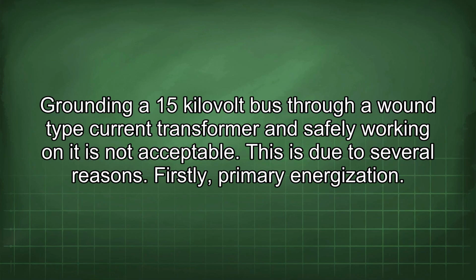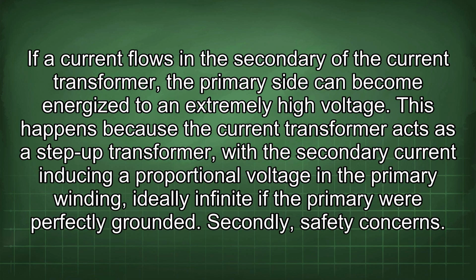Grounding a 15 kilovolt bus through a wound-type current transformer and safely working on it is not acceptable. This is due to several reasons. Firstly, primary energization. If a current flows in the secondary of the current transformer, the primary side can become energized to an extremely high voltage. This happens because the current transformer acts as a step-up transformer, with the secondary current inducing a proportional voltage in the primary winding, ideally infinite if the primary were perfectly grounded.